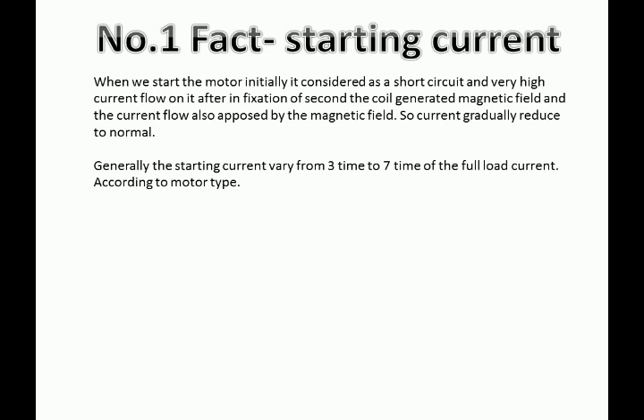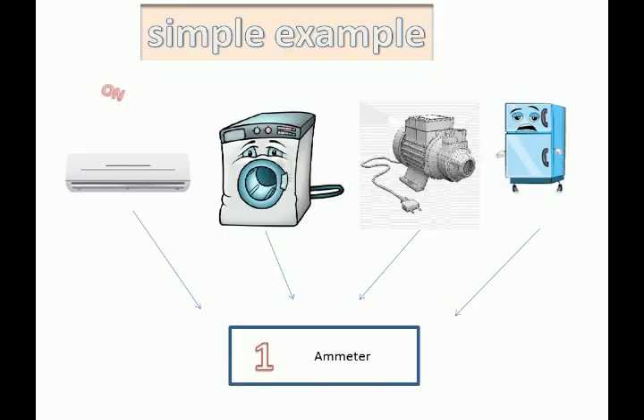Generally the starting current varies from 3 to 7 times of its full load current, depending on the type of motor. This we can see with a simple example.